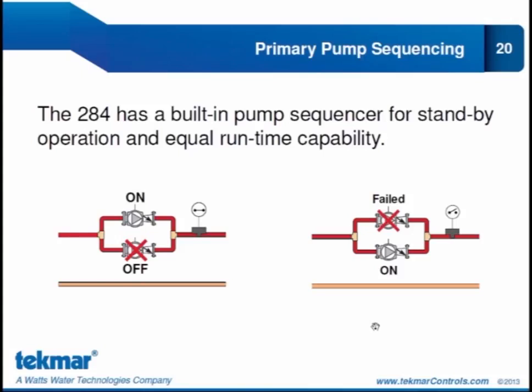Well, this is because emergency service calls are expensive and service contractors want redundancy so that if a pump fails, a lag unit automatically turns on. So we're going to try that twice to make sure before we shut the system down there is indeed a problem.